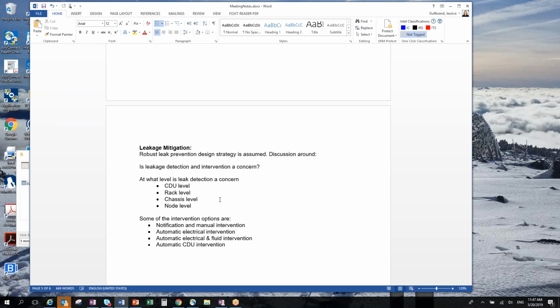And if it is, at what level is it a concern? There are many different ways to deal with detection, for example. Is detection at the CDU level good enough, or rack level, chassis level, node level? The finer the detail, going from CDU to node, the more added cost. And for intervention options, is getting notified with manual intervention good enough for leakage, or do you want a safe shutdown of your IT equipment, or a safe shutdown plus fluid depressurizing?